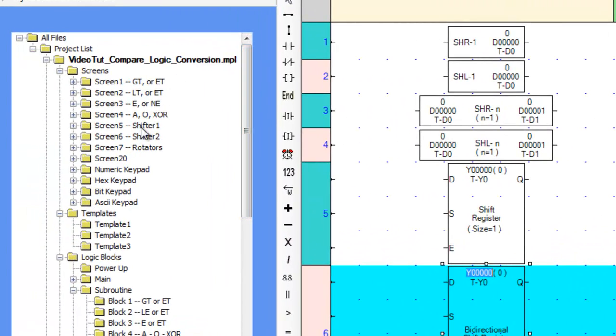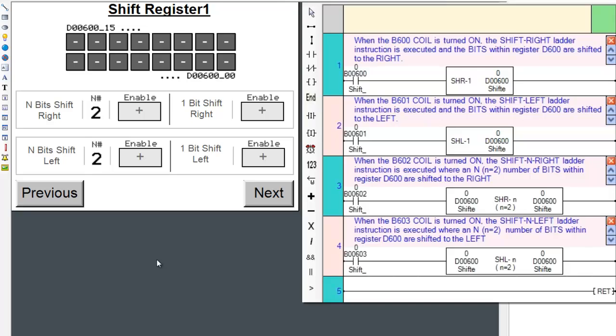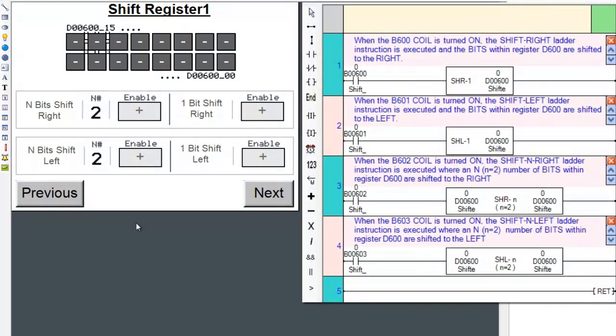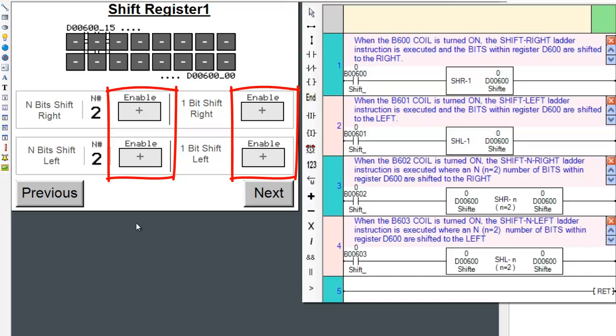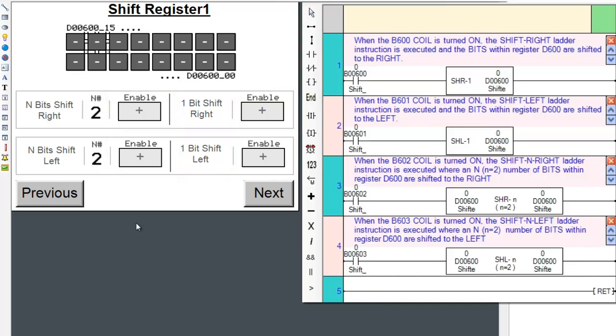Now let's observe screen number 5 and place the appropriate ladder logic subroutine on the right of the screen. Notice the block of buttons on the top center of the screen — each button is a toggle button. The top left button is addressed to register D600's 15th bit, the next to the 14th bit, and so on until the 0th bit. Please review the logical operators video tutorial for information regarding individual bits in data registers. The individual enable buttons execute the appropriate ladder logic instructions to move one bit or n number of bits right or left.